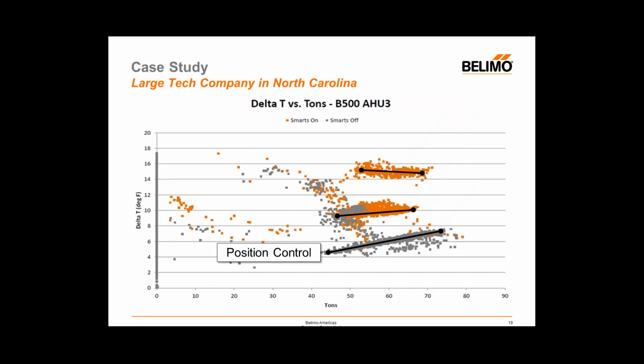Now, for fairness' sake, there's a whole bunch of gray points scattered all over the rest of this graph, but the clear trend was in this lower range. So sometimes they got better performance, but more frequently than not, they were getting this 4.5 to 7.5 degrees delta T. A couple of weeks went by and they changed their control strategy from position control to what we call flow control, where the control signal is now controlling how many GPMs of water go through that coil. So this would be in line with your pressure independent type control valve.